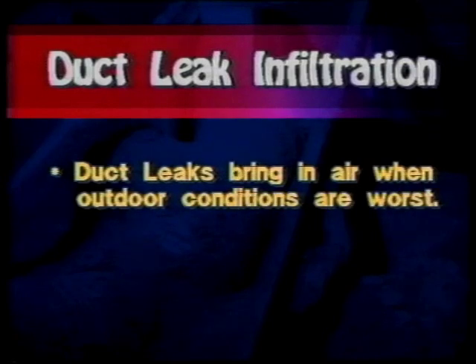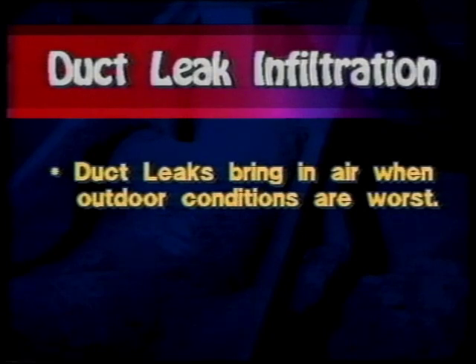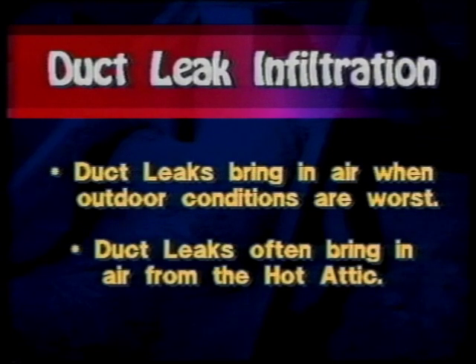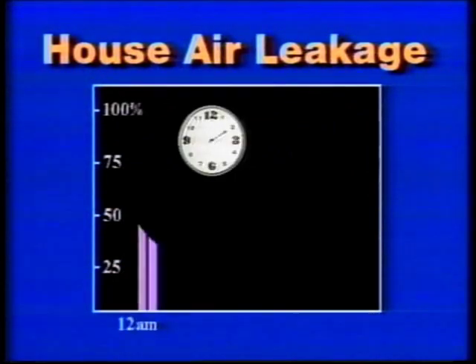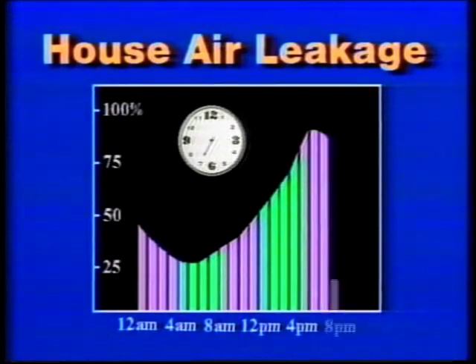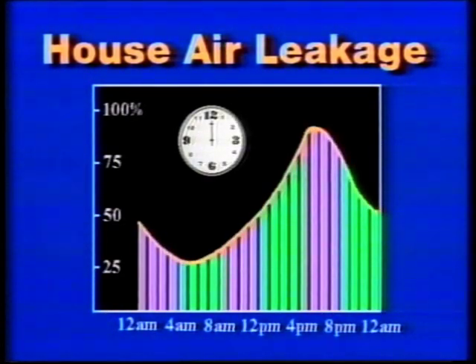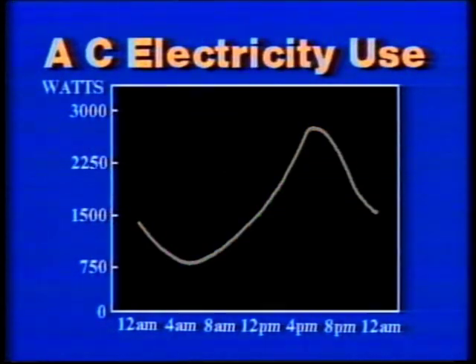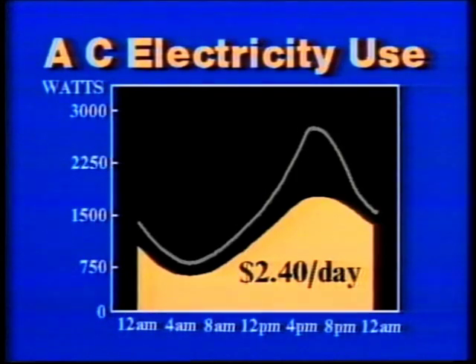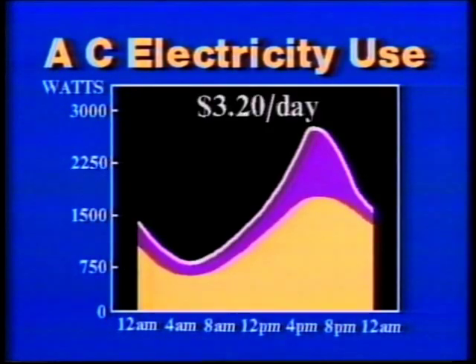The effects of duct leak infiltration are worse than we might imagine, for two reasons. First, duct leak infiltration only occurs when the air handler is operating, which is mostly when outdoor conditions are at their worst — on hot summer afternoons and cold winter mornings. Therefore, the temperature of the air brought into the house is hotter and colder than average outdoor air. Second, duct leaks often draw hot attic air into the house, so the impact on air conditioning is even greater. In the typical Florida home, air conditioning consumes about $2.40 of electricity per day with no duct leaks; duct leakage increases that to about $3.20 a day — a 33% increase.